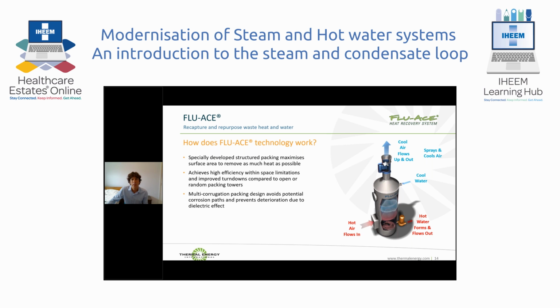If our fan was not running, then the exhaust gases would just continue up the existing stack. We then directly shower cold water through a system of nozzles and showers over some special packing material that provides residence time and contact between the water droplets and the rising exhaust gases. You can get very close approach temperatures. If we have cold water at 10 degrees C coming in here in sufficient volume, we can actually cool the exhaust gases down to around 12 to 15 degrees C.